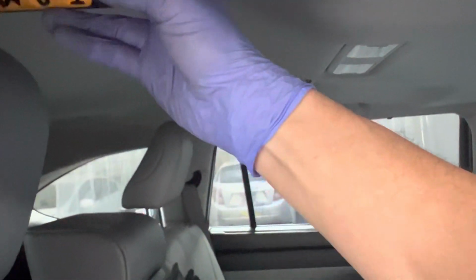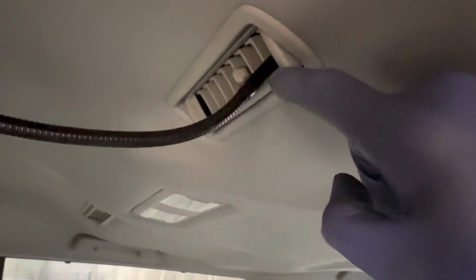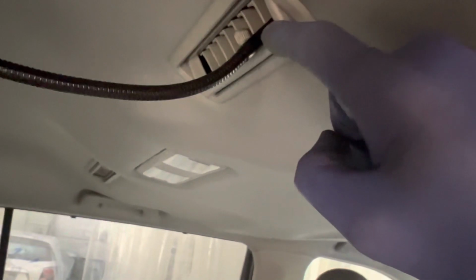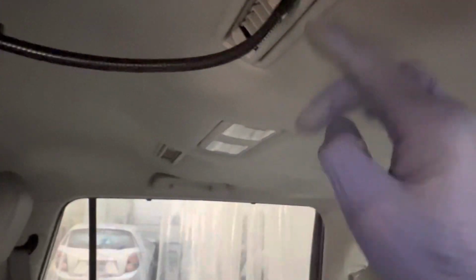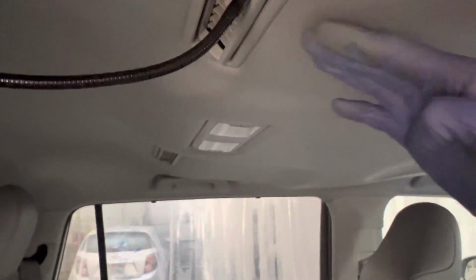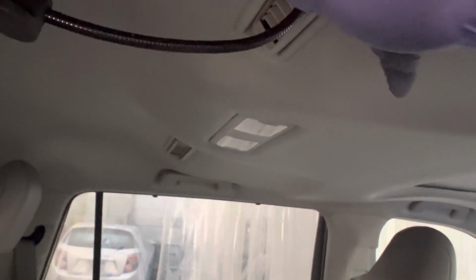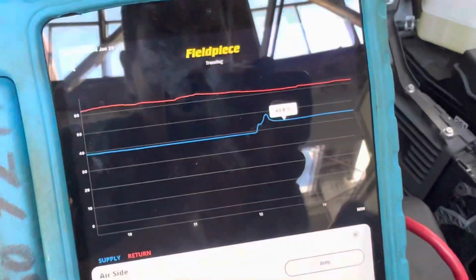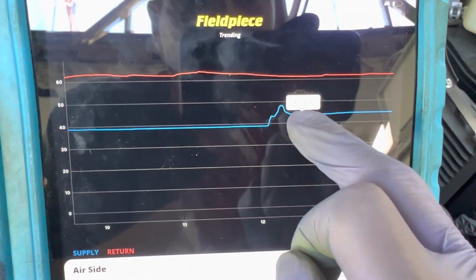Uh-oh, I think I'm going to have an issue. Okay, that is not good because you see how my tip is almost out of the fins right there? The air at this point is not the same temperature as the air in here. As this flows out and I have my sensor right here, warmer air from inside here also mixes right at the tip there, and a little bit of air gets entrained and mixed with the cold air. So it might be a little hotter because I can't get it to stay. Oh, still doing good. So in the very rear we were 43.9, now 44.5, within 1 degree.